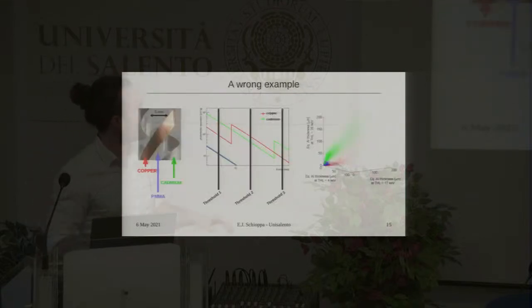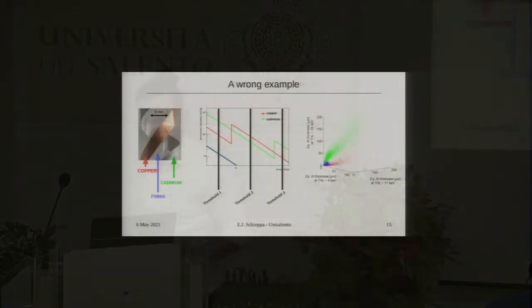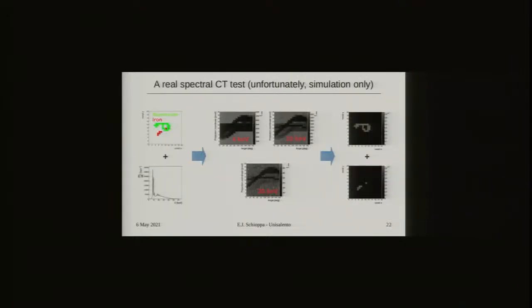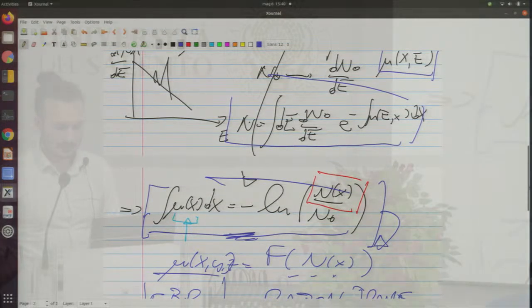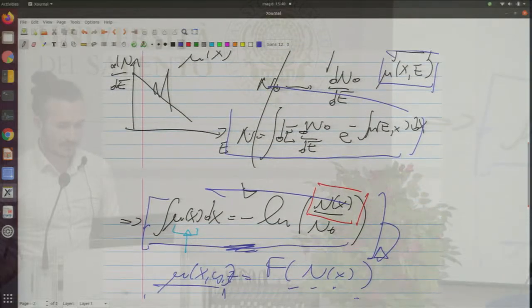But here you just looked at how the values of the reconstructed images at different thresholds are correlated, according to that plot on the right. If you do this properly, you are going to include this information in the image reconstruction algorithm. You can do it, I don't say easily, but if you already start from a formula of this type, and then you include the fact that your detector now is measuring not over all the energy range, but from a threshold up to infinity.